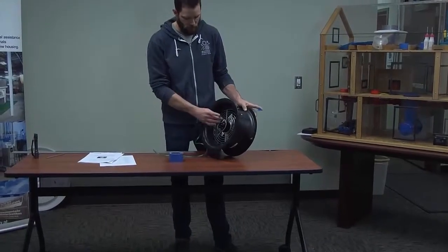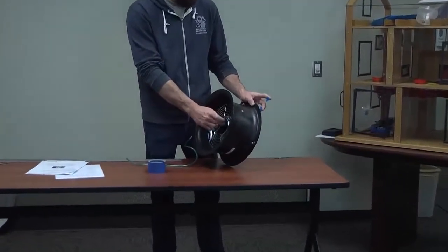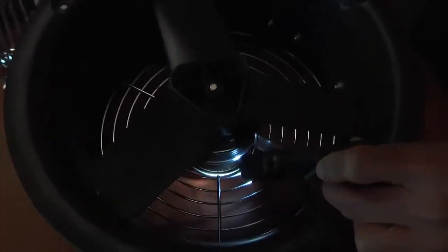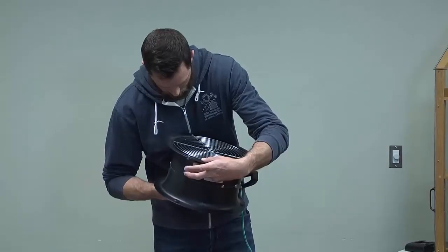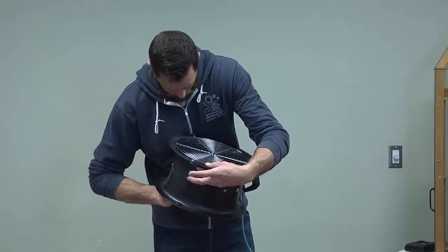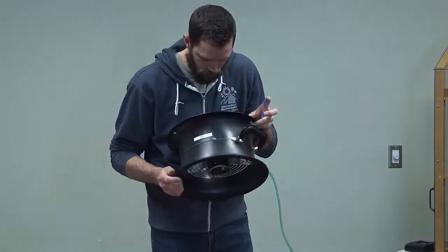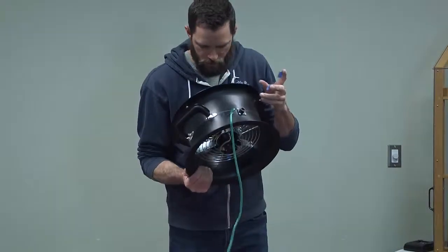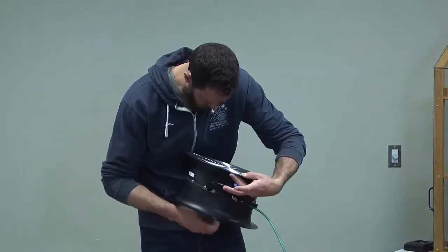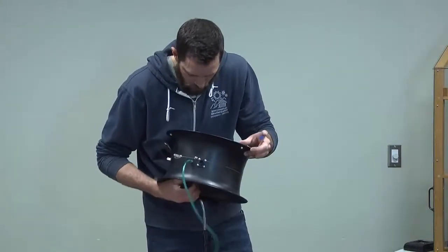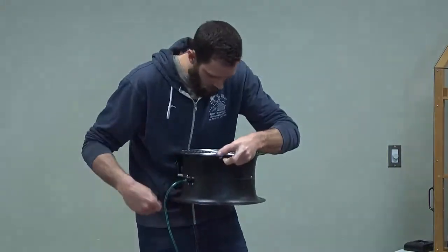So the holes on this flow sensor, they're really tiny and they're on the back side of the tube. So you have to turn the Duct Blaster upside down and look behind that tube on the back side to see where you're taping. And there's 3 of them. And they're kind of evenly spaced around the tube.